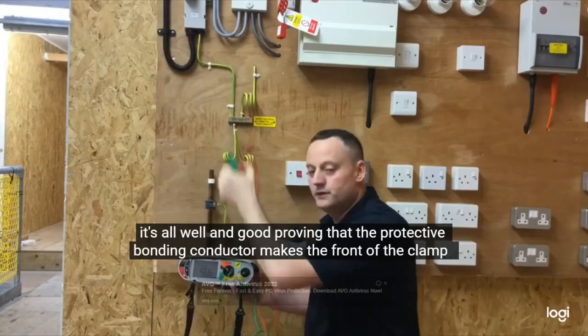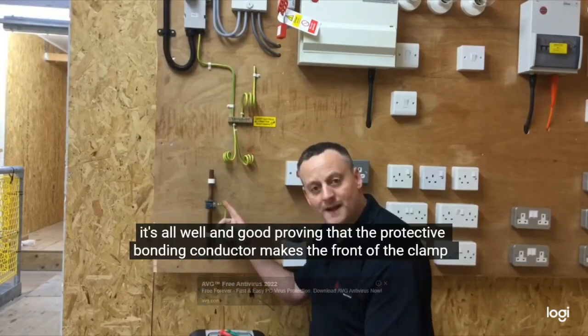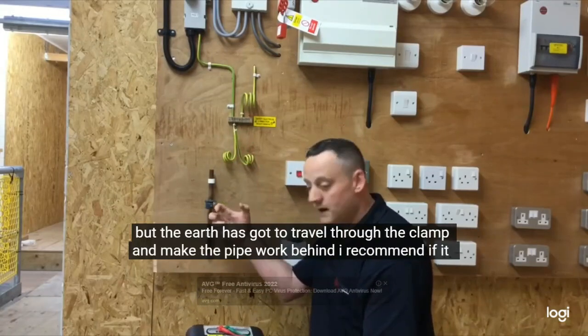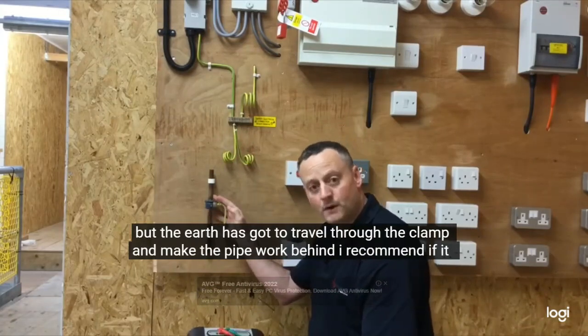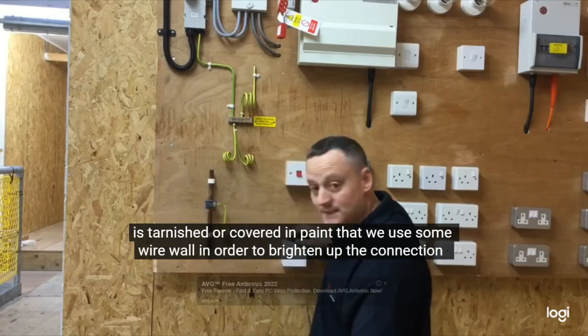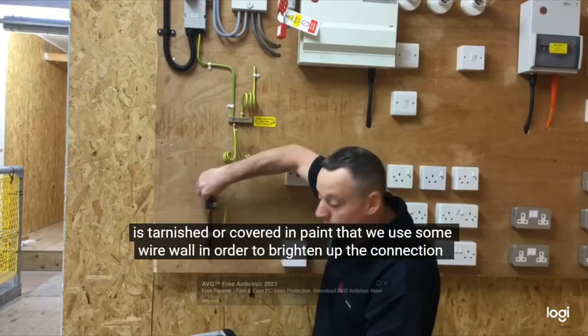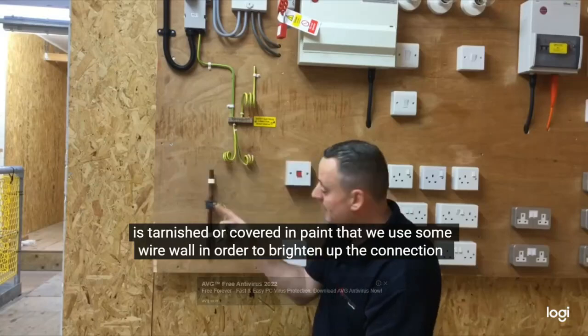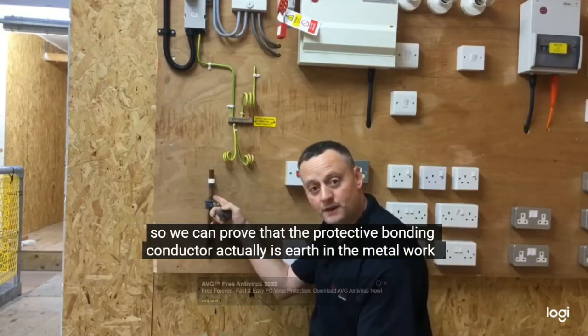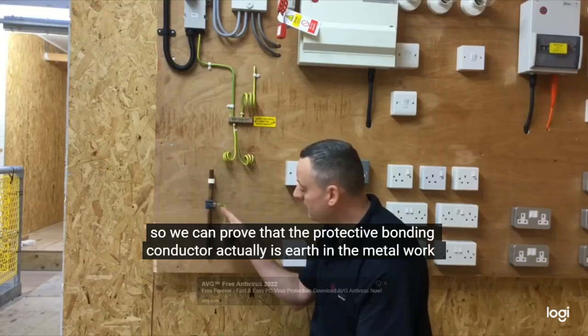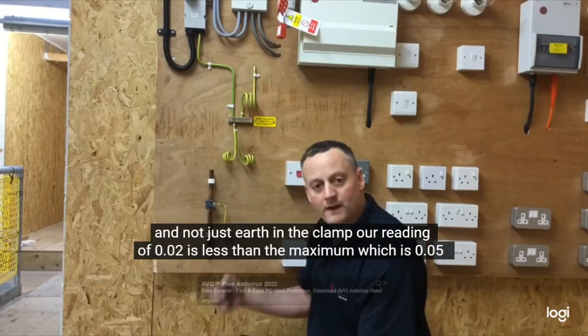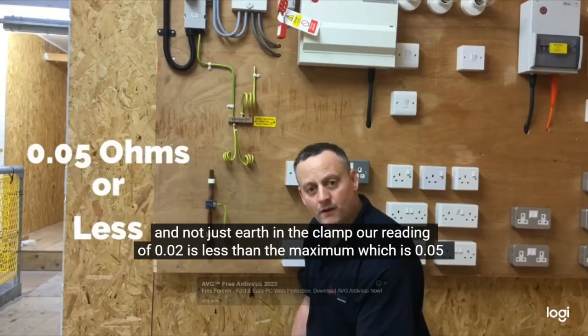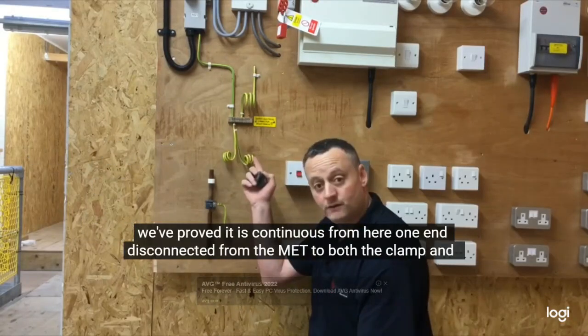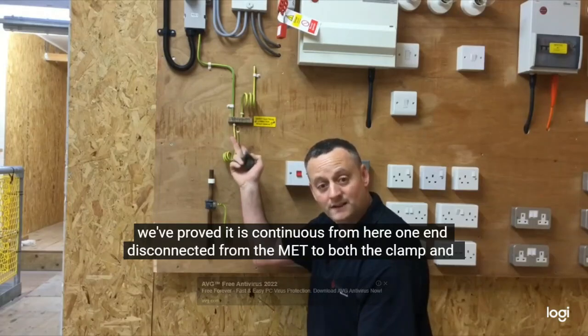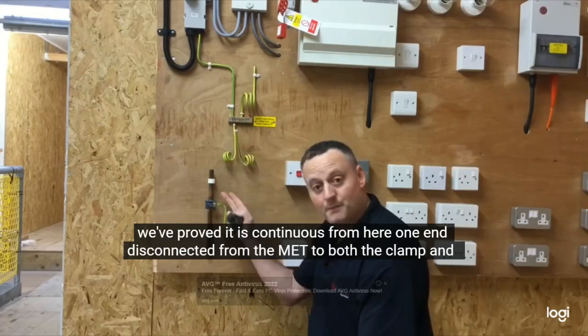It's all well and good proving that the protective bonding conductor makes the front of the clamp, but the earth has got to travel through the clamp and make the pipework behind. I recommend if it is tarnished or covered in paint that we use some wire wool in order to brighten up the connection so we can prove that the protective bonding conductor actually is earthed to the metalwork and not just earthed to the clamp. A reading of 0.02 is less than the maximum, which is 0.05. We've proved it is continuous from here, one end disconnected from the MET, to both the clamp and pipework.